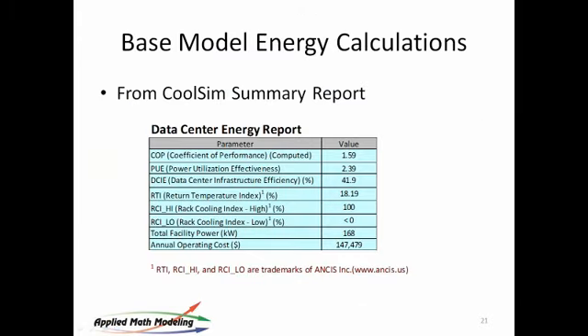So here's what came out of it. This is the actual plot of the data center energy set that we were looking at. And you see here that the RTI is 18. The RCI high is certainly fine, no racks are over temperature, but we've got a problem here with low. So we're wasting energy. The estimated cost to run this data center for a year is about $150,000.